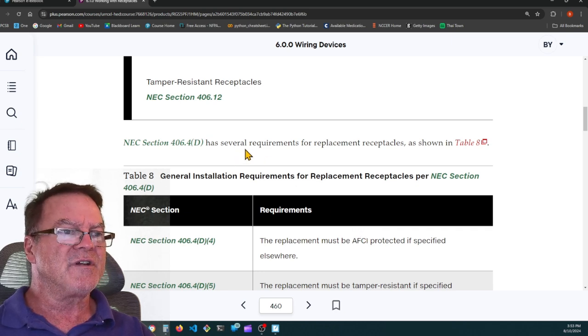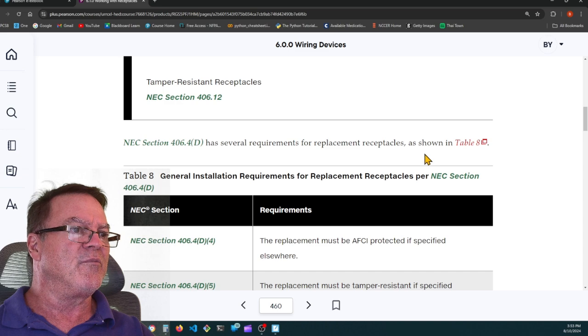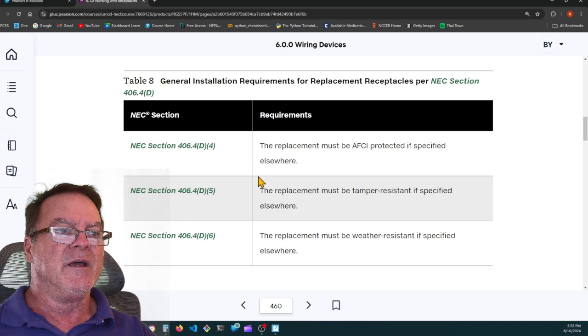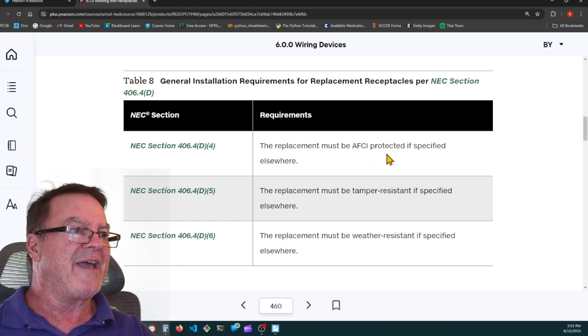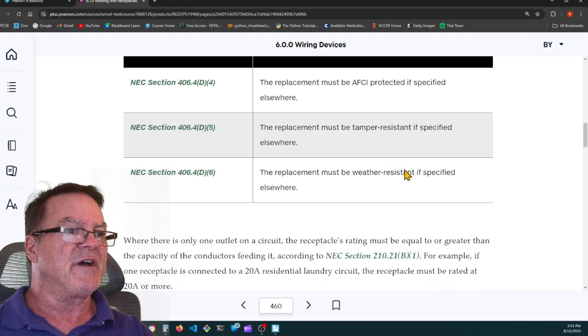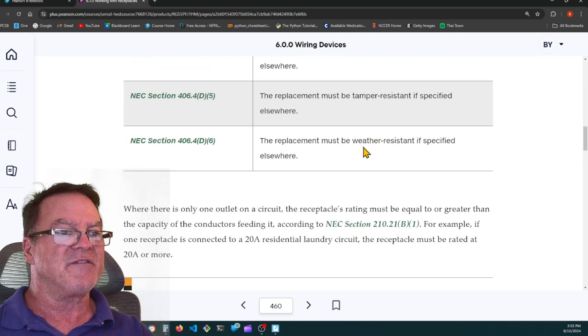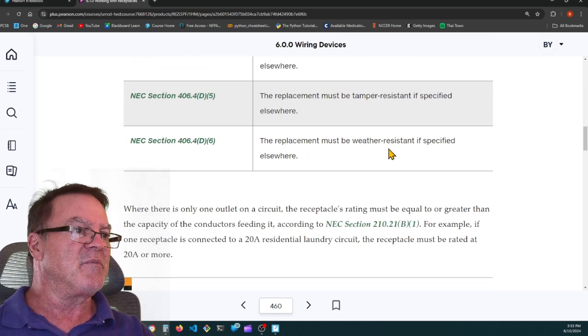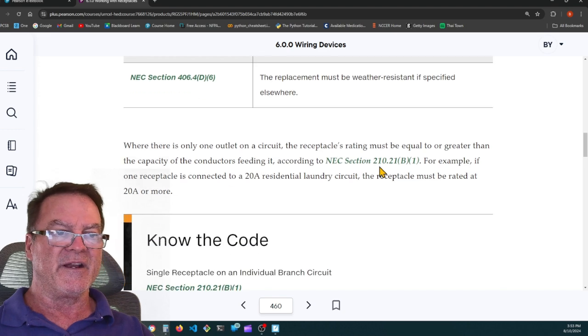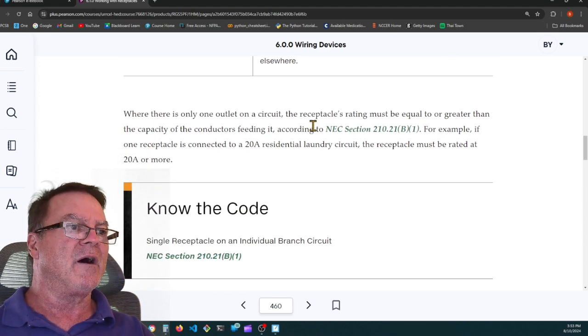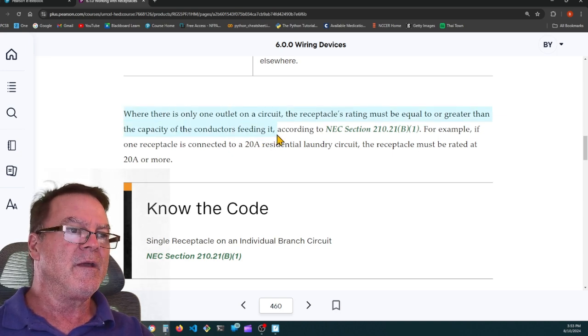NEC Section 406.4(D) has several requirements for the replacement receptacles as shown in Table 8. So, the replacement must be AFCI protected if specified elsewhere. The replacement must be tamper resistant if specified elsewhere, and the replacement must be weather resistant if specified elsewhere. Where there's only one outlet on a circuit, the receptacle's rating must be equal to or greater than the capacity of the conductor feeding it. That sounds familiar. There.